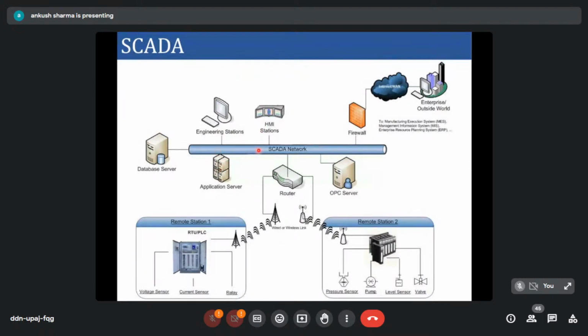This information goes to your HMI station, where you see the single line diagram and the parameters captured from the field. You may need to store the data for historical purposes, and if you want to share data to another control center or to the outside world, you can do so through a firewall to an external network. This is how the SCADA system works in the control center.